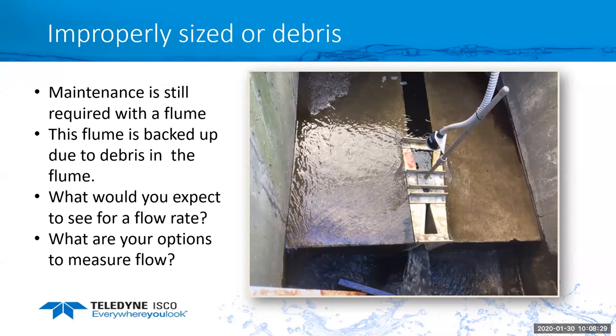So what would you expect through this? You're still going to get a flow rate reading, but it's going to be much higher than the actual flow going through there. But what are your options on this? One, set up a regular maintenance schedule to clean the flume out, or two, have an alarm set that if it ever gets to a maximum flow rate, somebody needs to go out and inspect it. Or the other option is to put an area velocity sensor upstream, because an area velocity sensor will read the level and the velocity. In this case, it would read a high level but almost zero velocity to give us an accurate flow rate.